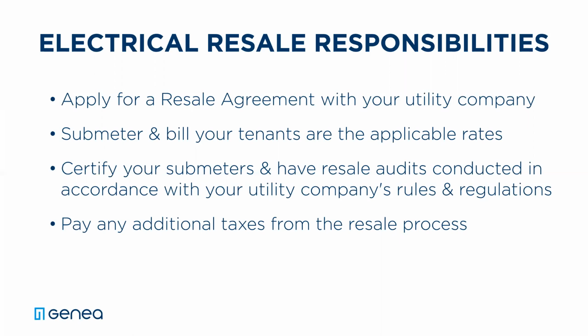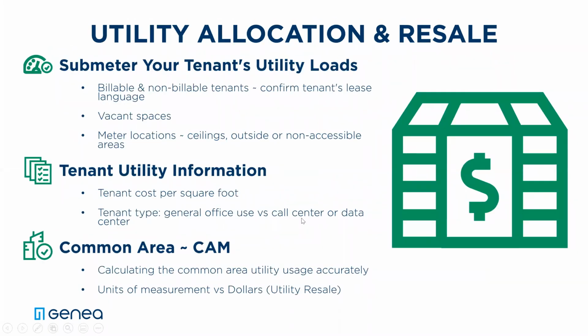In most cases, you can reach out to your utility company, but if the meter, the utility meter from the main utility company, is before the transformer, then in most cases you own that transformer. If it's after the transformer, then in most cases the utility owns that transformer. But you can definitely reach out to your local utility - they'll be able to let you know.